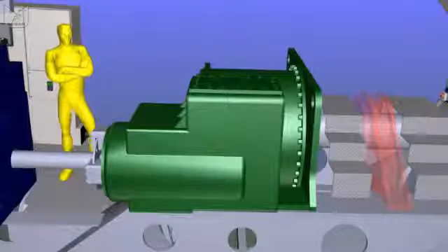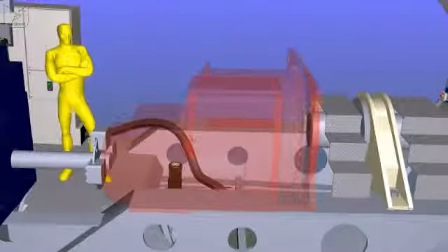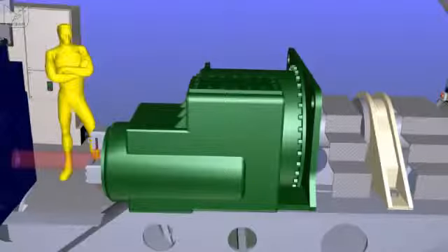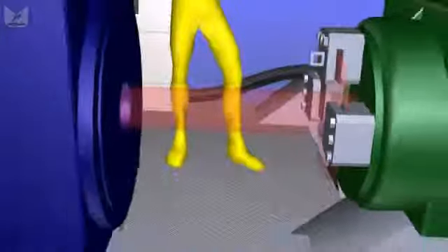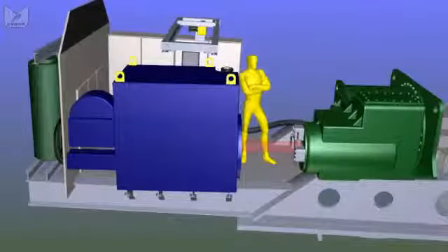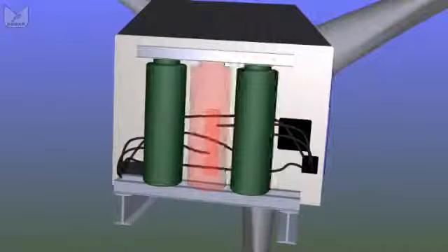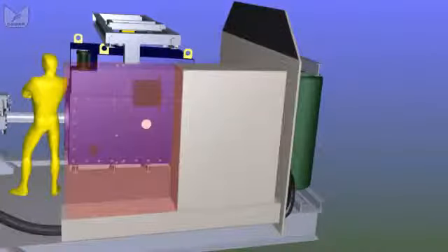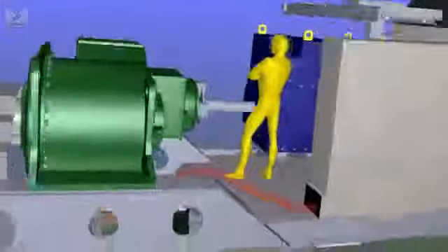So our main shaft drives our gearbox, which is mounted centrally because it's often the heaviest component. Out of the back comes a high-speed shaft, as before. That's where the braking system is. The high-speed shaft then drives the generator, which is usually oil-filled. The generator then supplies 690 volts, in this case into our transformer, which is sitting right next to it. That high voltage signal then passes through the switchgear and the cabinets, down the dropper cable, straight down to the bottom of the tower, through those switches on platform 2 and off to the substation.